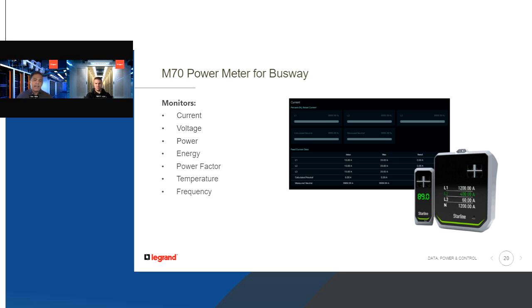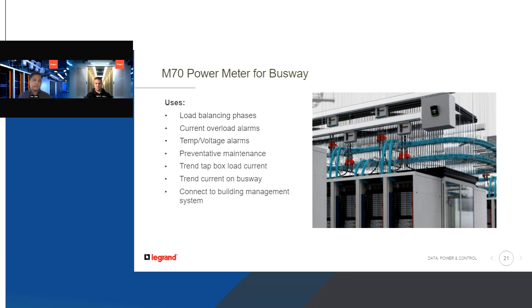With respect to AI and monitoring in general, it lets you load balance and set alarms for preventative maintenance. Centering this around AI, it really lets you trend current data going to the rack. If you connect this metering system to a building management system, you can take snippets in time and profile whatever load the plugin is powering, and see what peaks and valleys are happening within a particular rack.